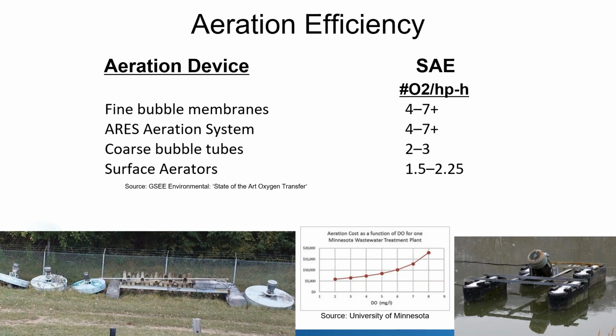But if you're running more DO than you need, if you set it and forget it, you just run your system full blast, even though your ADF may be a quarter of your peak, where that sizing was, look at how rapidly, and again, University of Minnesota doing some great research that I'm happy to be able to share here, publicly available. But I mean, look at that. Look at how much you can put a dollar value on each additional milligram of dissolved oxygen in your residual. What better way to make the point for running your system properly and efficiently?